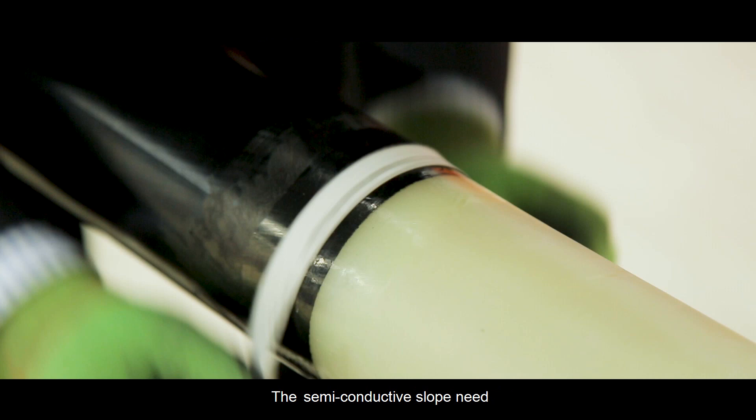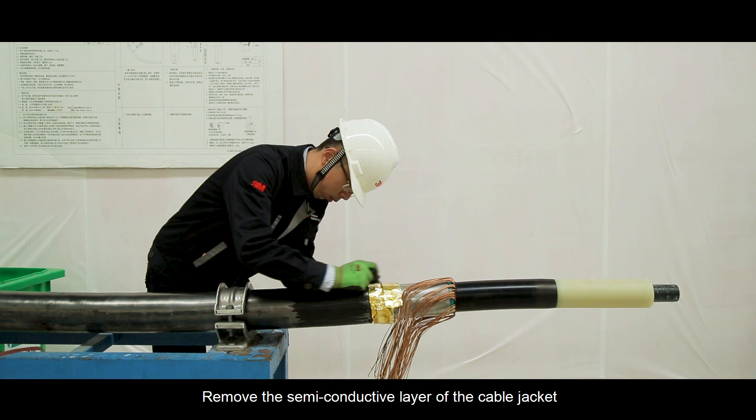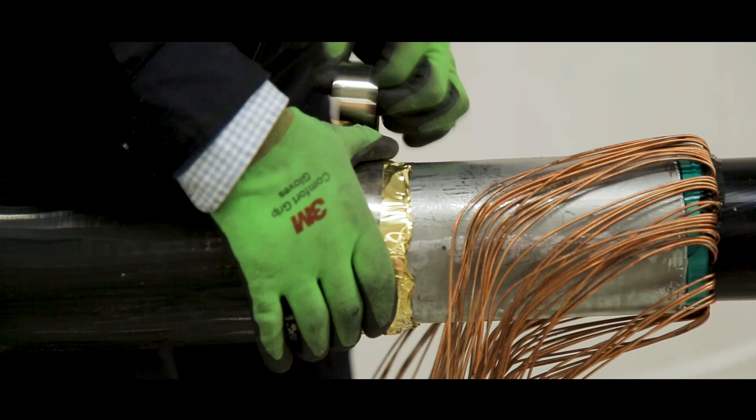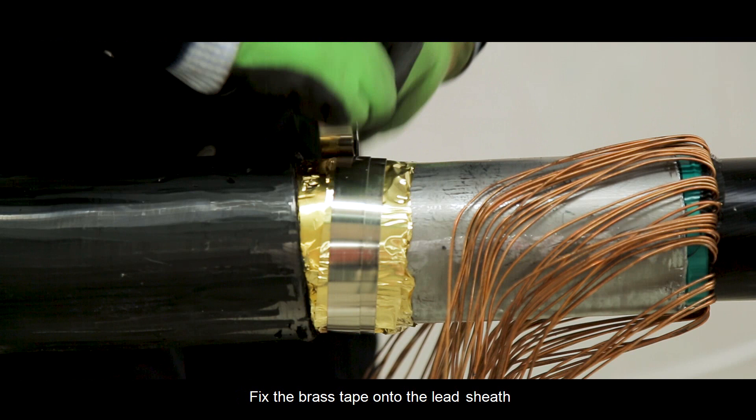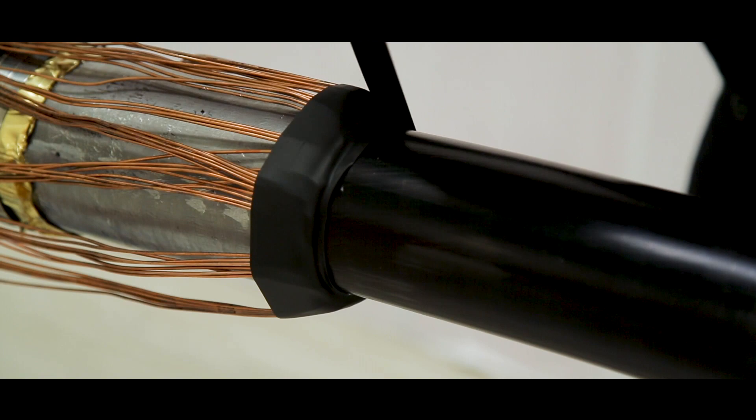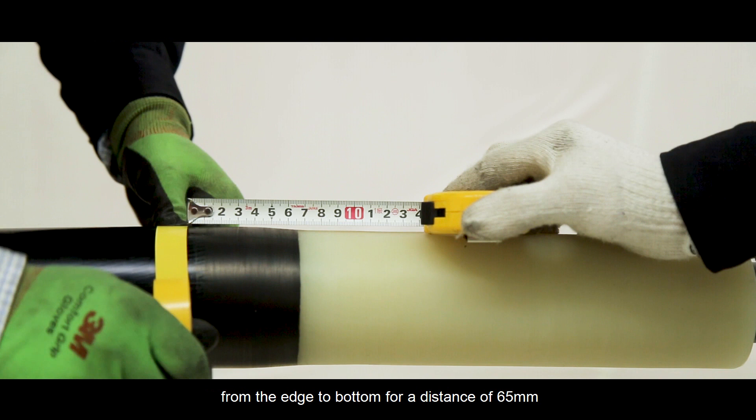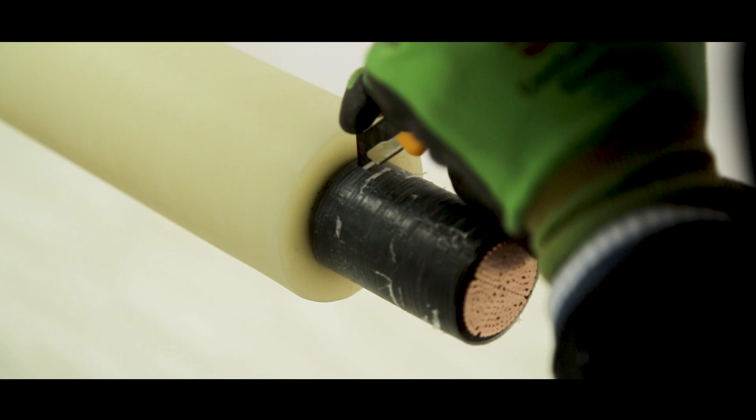Remove the semi-conductive layer of the cable jacket for a distance of 200mm to 300mm. Fix the brass tape onto the lead sheath using constant force springs. Make a mark on the semi-conductive layer from the edge to bottom for a distance of 65mm.